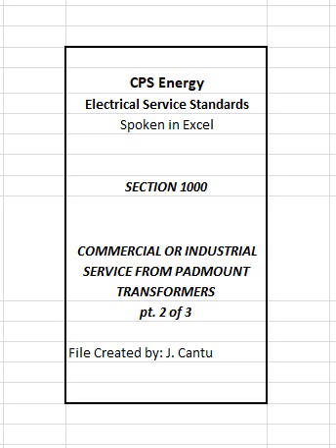3. Allow for 6 feet of clearance in front of transformer slab, transformer door side, and 3 feet around sides and back. If possible, transformer doors shall face away from buildings or structures. 4. Appropriate clearances for transformer away from building openings, stairways, fire escapes, etc. 5. No exposure of transformer to corrosive vapors, steam, cooling tower discharges, etc. that could damage it. 6. Protection by use of removable concrete-filled bollards around transformer where it is subjected to vehicular traffic.